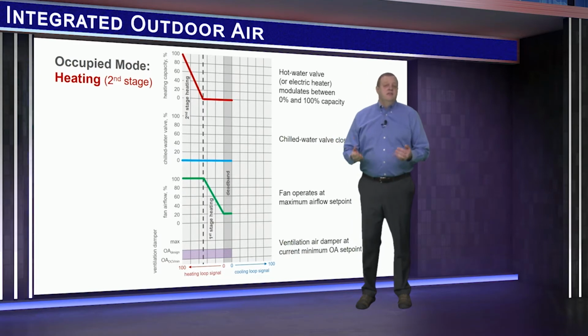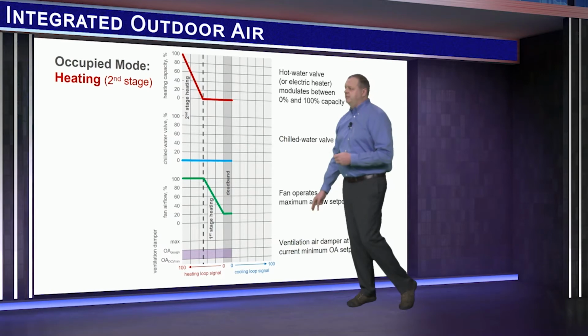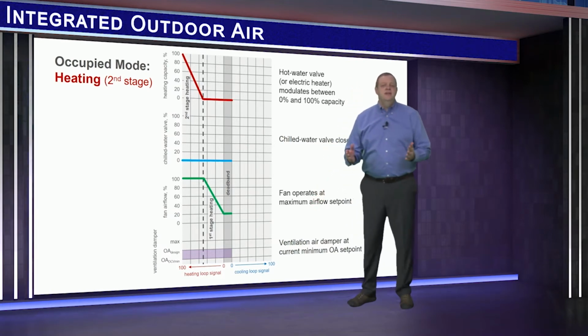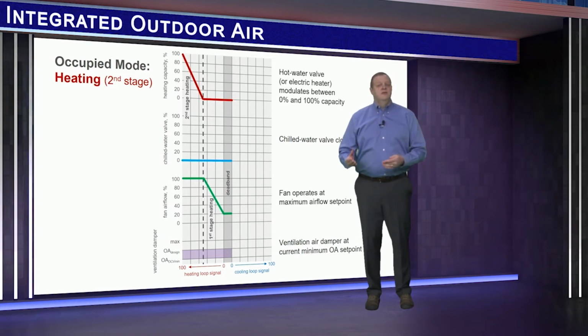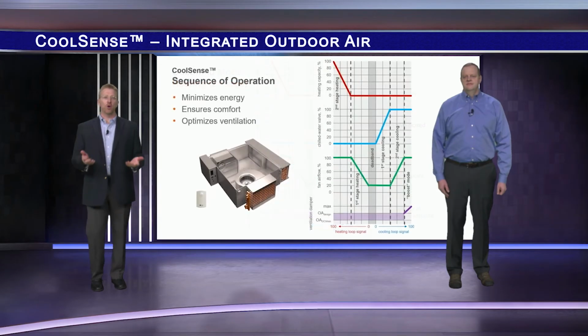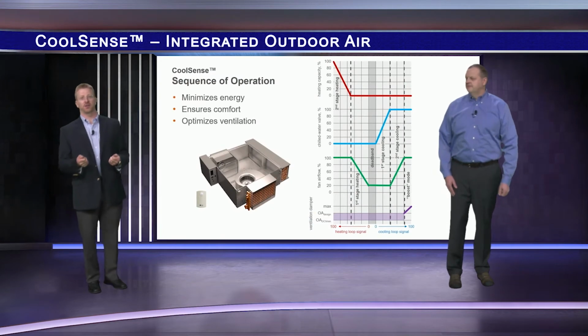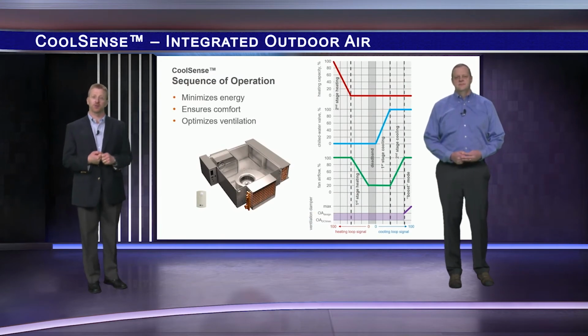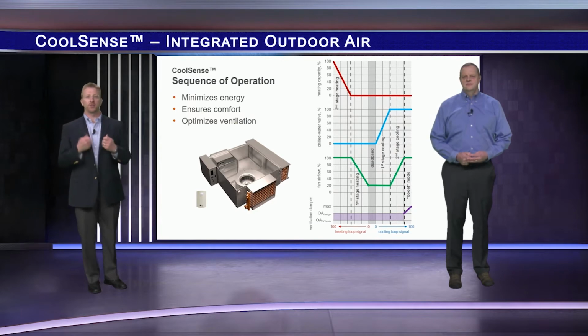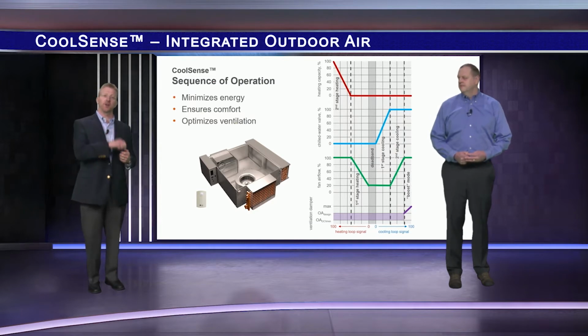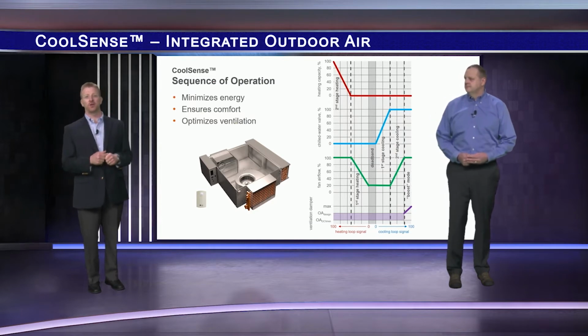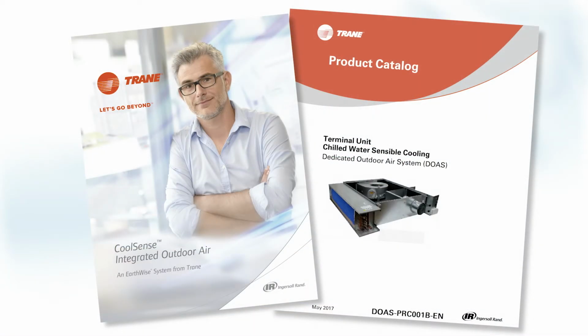Now in heating mode, the ventilation damper is controlled to the current minimum outdoor airflow set point. There is no boost mode for heating since the temperature of the ventilation air is typically not warmer than the zone during occupied mode. We hope this explanation offered the necessary details to demonstrate how these CoolSense terminal units operate. It should be noted that these control strategies are integrated directly into the factory unit-mounted controller. If you want to learn more, it can also be found in the CoolSense Systems catalog or the Terminal Unit catalog.